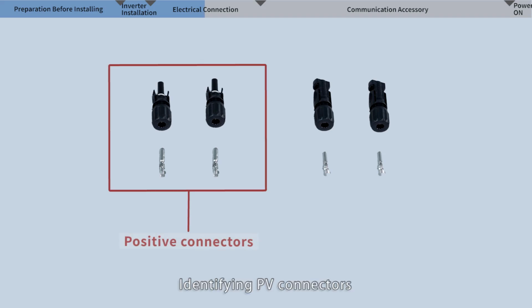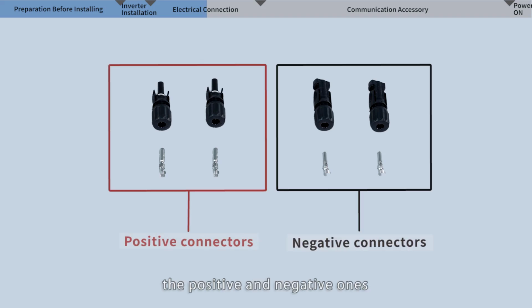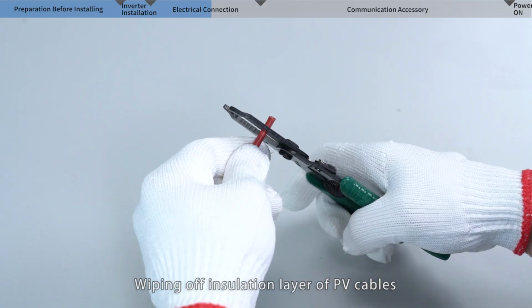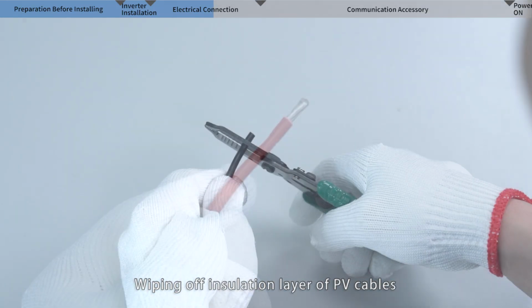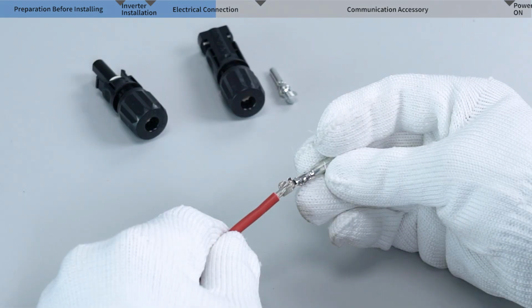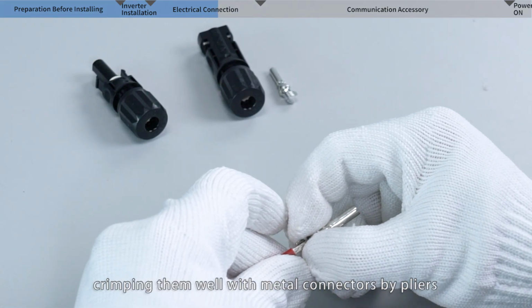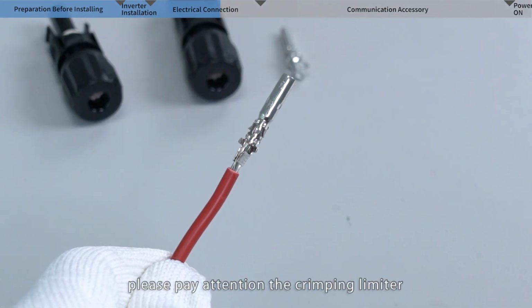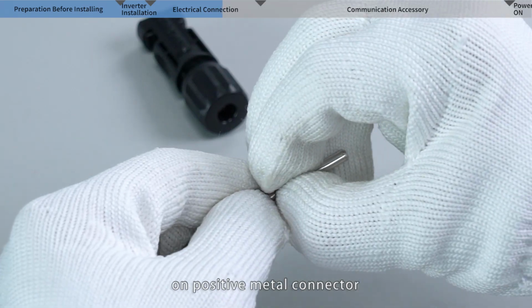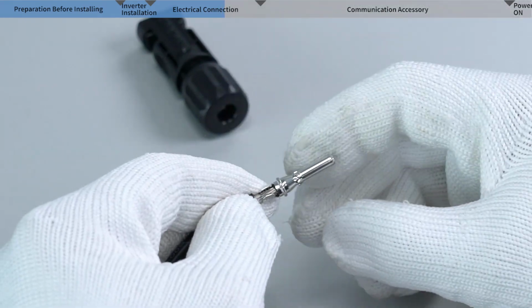Identify the PV connectors, the positive and negative ones, as well as the metal connectors matching them. Wipe off the insulation layer of the PV cables. Crimp them well with the metal connectors using pliers. Please pay attention to the crimping limiter on the positive metal connector.